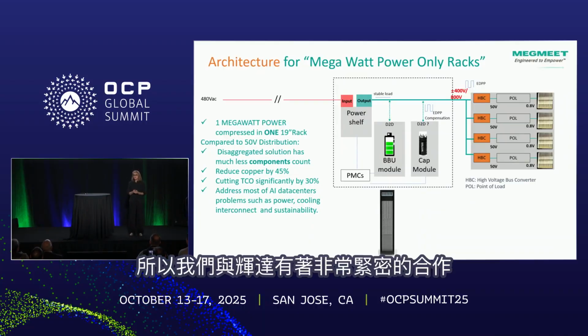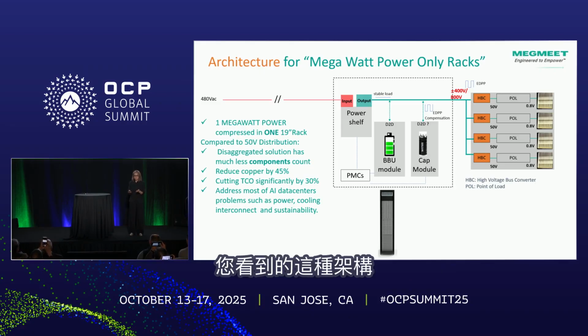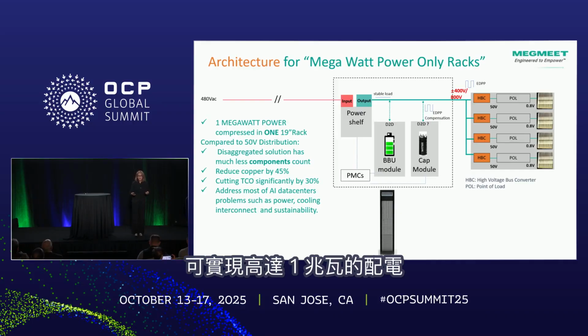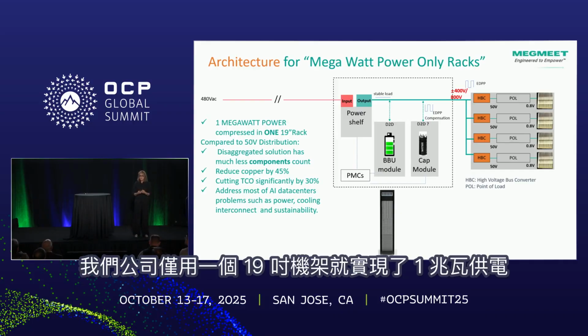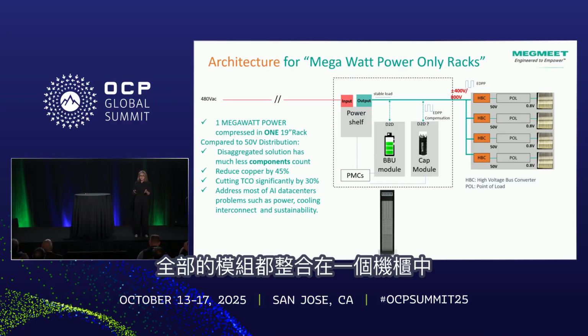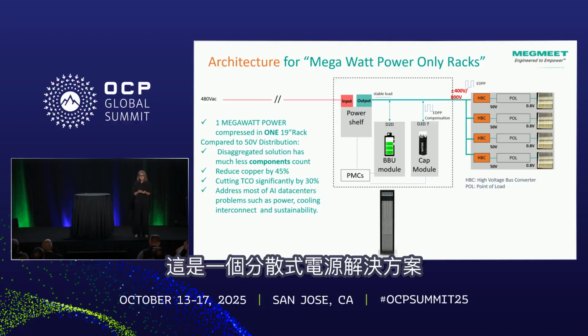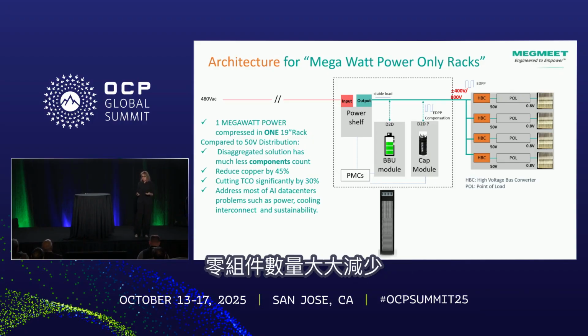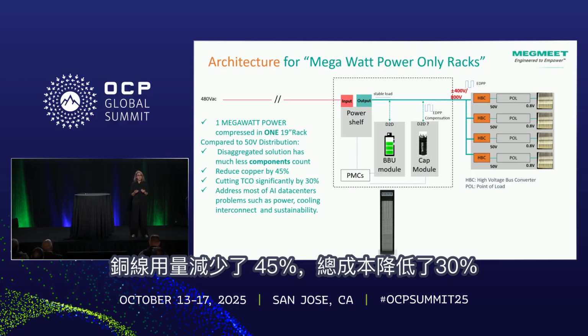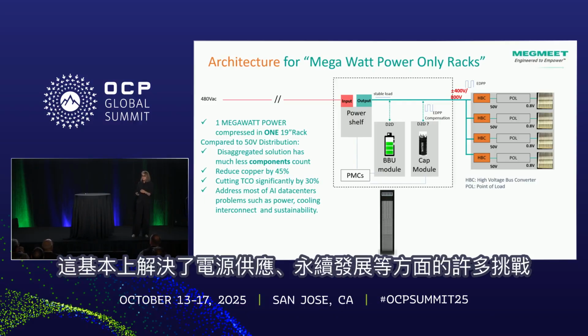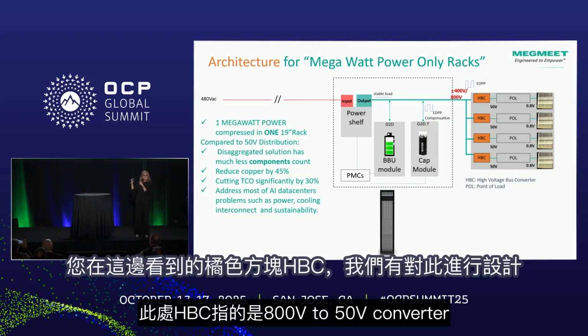So we have a very close collaboration with NVIDIA. This architecture that you see is allowing a power distribution to get to 1 megawatt. We at Megmeet, we did 1 megawatt in only 19-inch rack, and that is compressed in one rack. This is a disaggregated solution with much less components. The copper is reduced by 45%, the TCO by 30%, and this is basically answering a lot of challenges with power, interconnects, sustainability, and many more. There are some boxes you see in the orange. The HBC is also Megmeet design, so I will go through that.